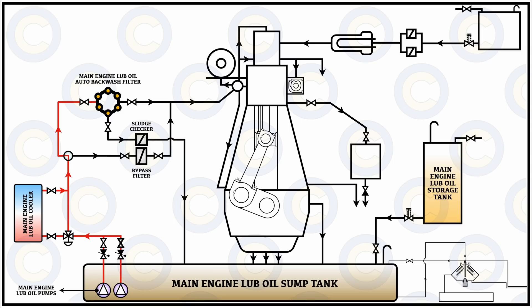Once the oil has passed through this system, it will go into the distribution manifold. From the common manifold, the oil will go to a number of places and lubricate the different bearings and parts of the main engine — for example, the crank pin side, the crosshead side, as well as the main bearing side. In different constructions, sometimes there might be a telescopic pipe or sometimes an articulate arm, depending on whether the engine is of MAN B&W or Sulzer design, with similar designs by other manufacturers such as Mitsubishi.